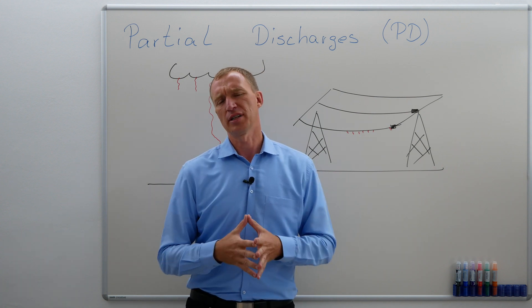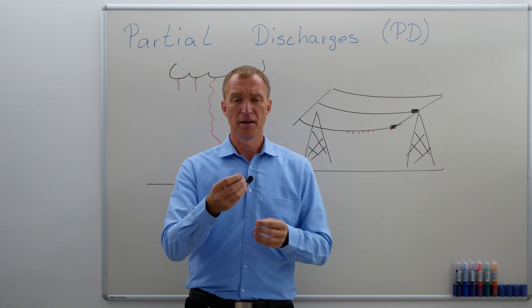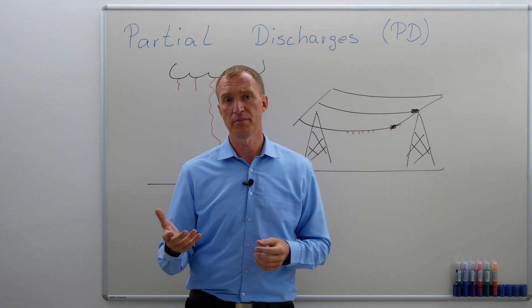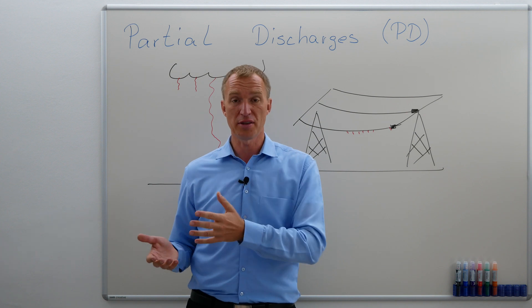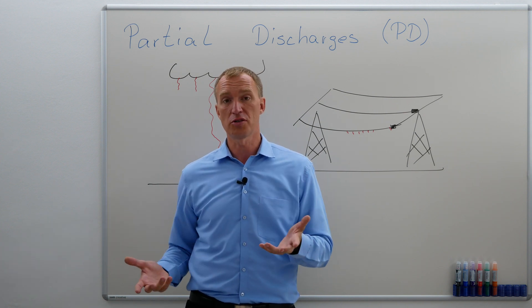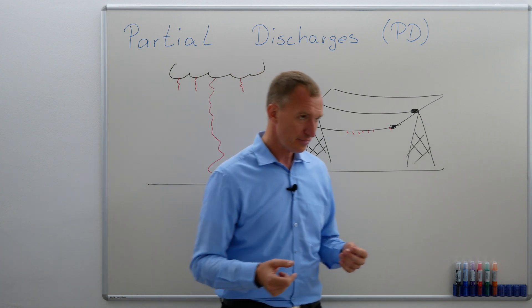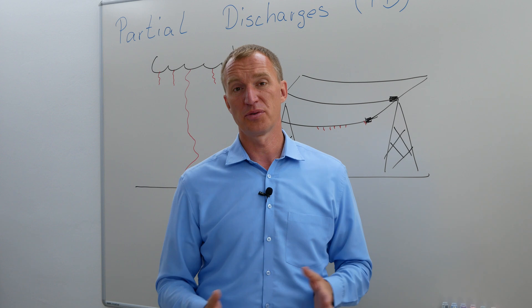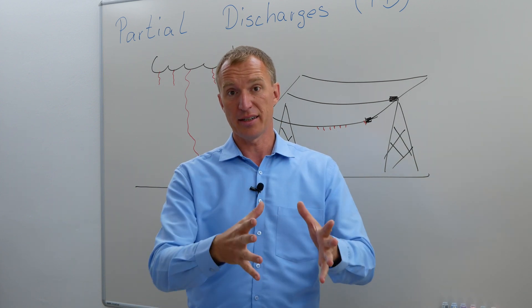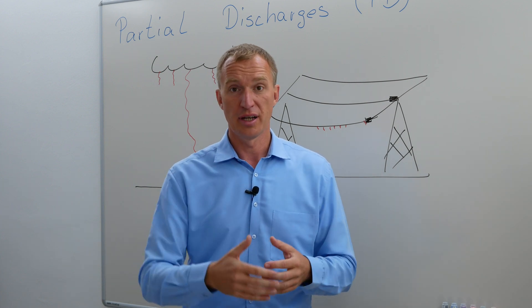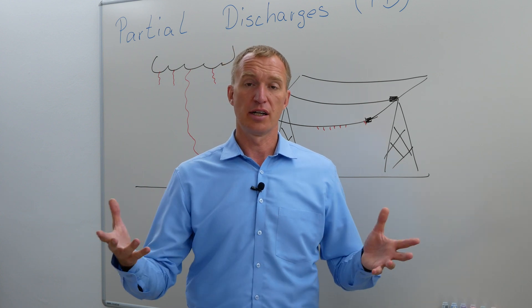Partial discharges are sometimes considered a little bit like cancer on a high-voltage insulation. It starts very subtle, but then it grows over time, destroying the insulation system, and very often it tries to reach the other electrode. Once it has reached the other electrode, we're going to have a full discharge. A full discharge on a high-voltage device is not very funny — it very often results in the destruction of the device, and if connected to the power grid transporting current, it usually results in an explosion.